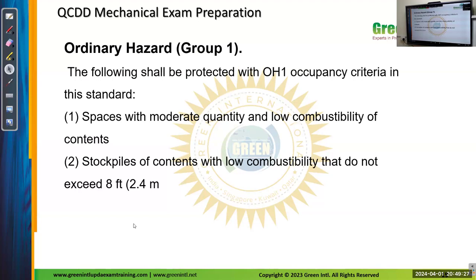So ordinary hazard group 1: spaces with moderate quantity and low combustibility of contents. Stockpiles of contents with low combustibility that do not exceed 8 feet or 2.4 meters. Stockpile means, for example, if you are dumping some material, or if you are putting paper in a rack. It should not be more than 2.4 meters. Stockpiles of contents with low combustible material that do not exceed 8 feet or 2.4 meters come under ordinary hazard group 1.